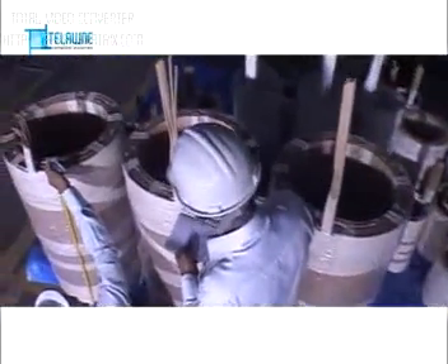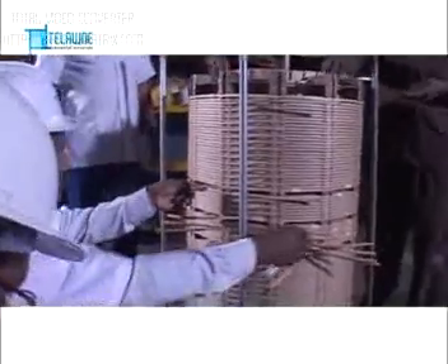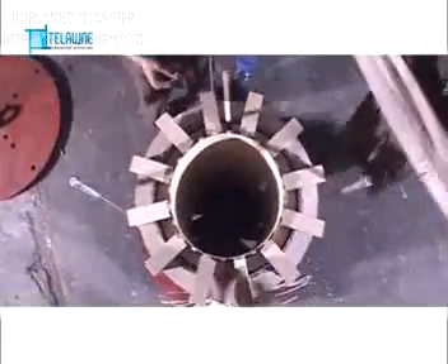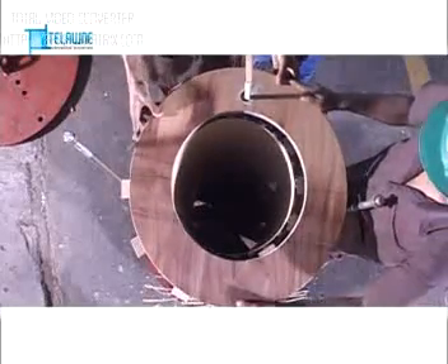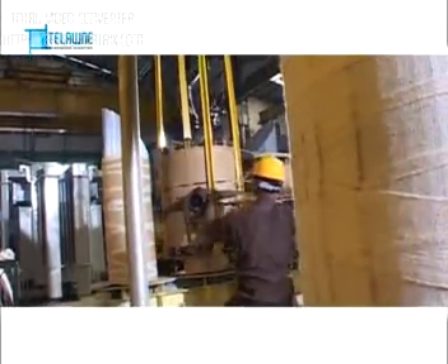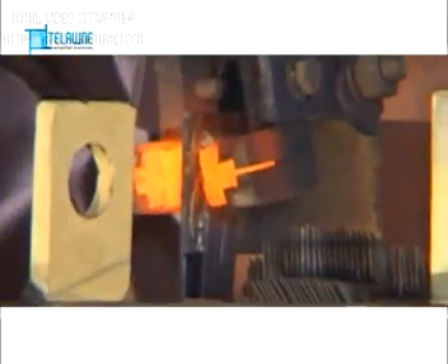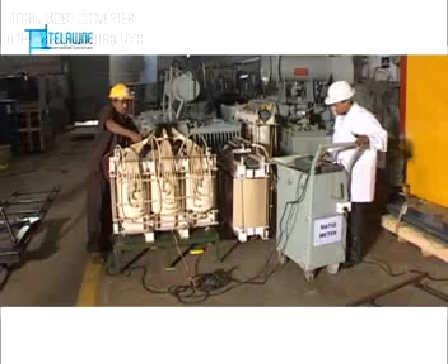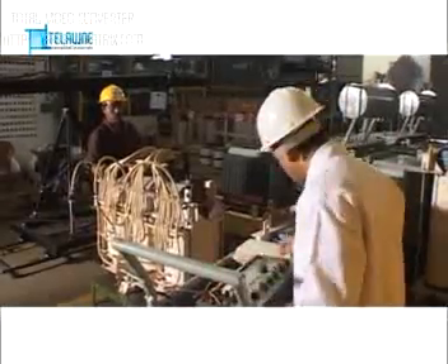After dimensional inspection and electrical tests, pressed coil composite assembly of each phase is done. All composite assemblies are again heated and pressed to ensure that height is maintained and assembly is symmetric. The composite assembly is then assembled on the core, and the connections are electrically brazed by silver phosphorus material for better conductivity. Intermediate inspection of core coil assembly is done by ratio test.